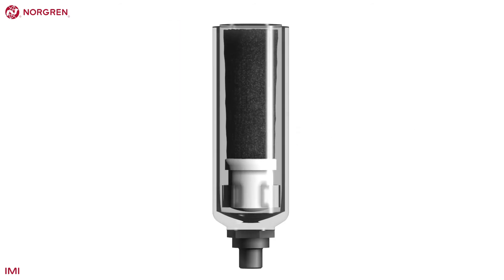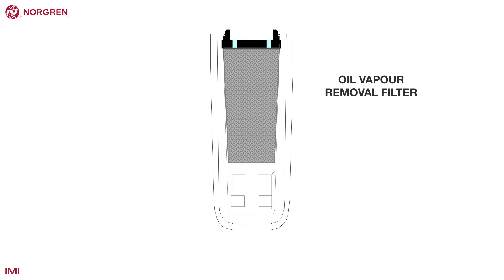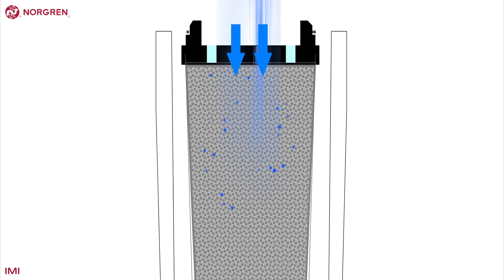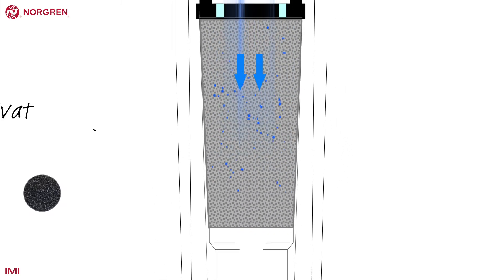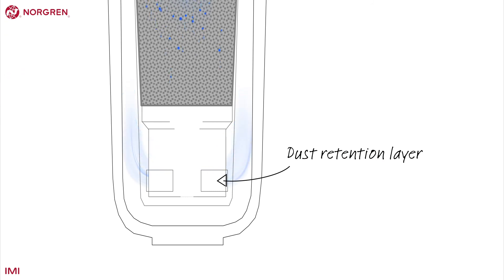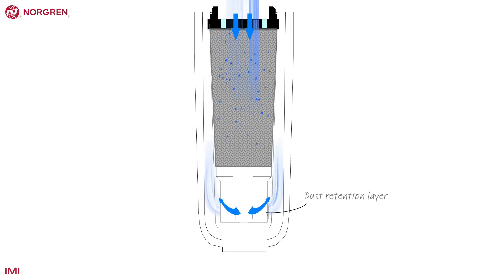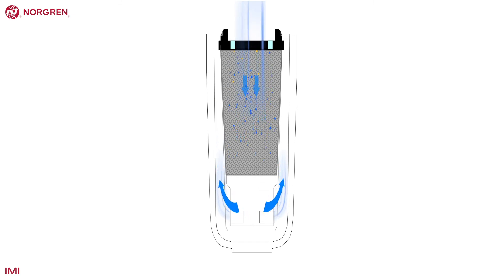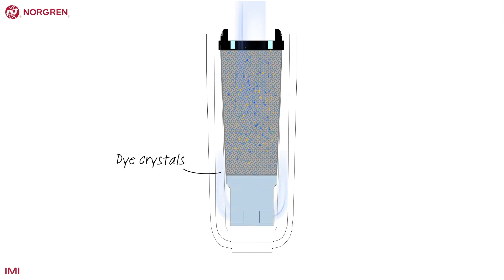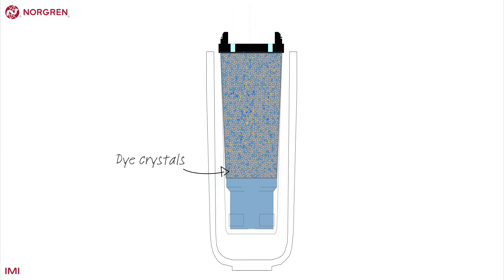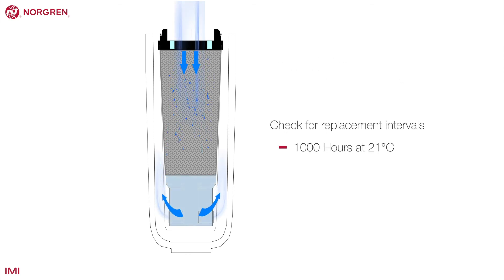An oil vapor removal filter uses activated carbon to extract oil vapor and odors from air. In a similar way to the coalescing filter, air is forced through an element, but this time the element is made of activated carbon that captures the oil particles at a molecular level. Once through the carbon, the air passes through a dust retention layer before exiting. There is no drain required as no liquid will collect. If the filter is exposed to liquid oil, it will no longer function and will need to be replaced. The carbon pack contains dye crystals that turn blue if exposed to these contaminants. If activated, it's important to understand the source of the problem. This element needs replacing rather than servicing. Check for replacement intervals and operating limitations regarding temperature.